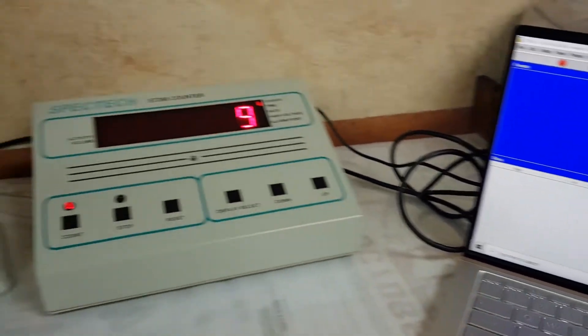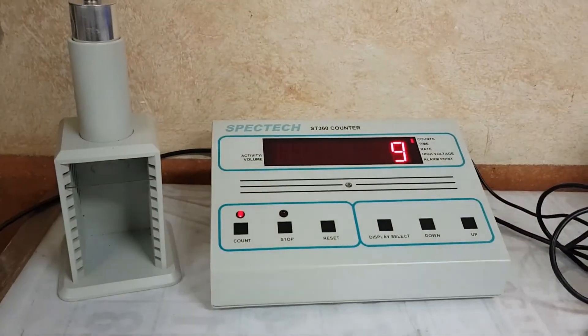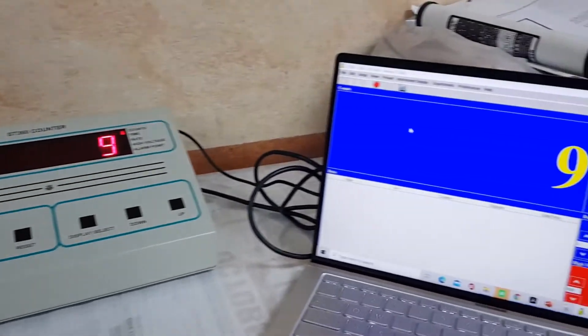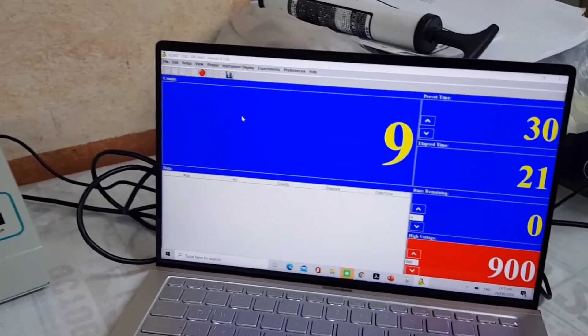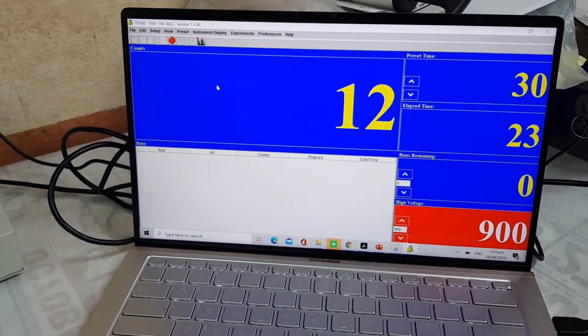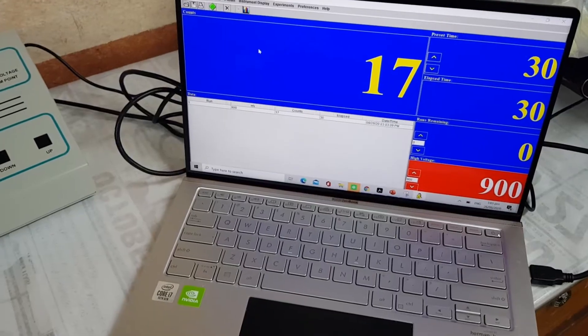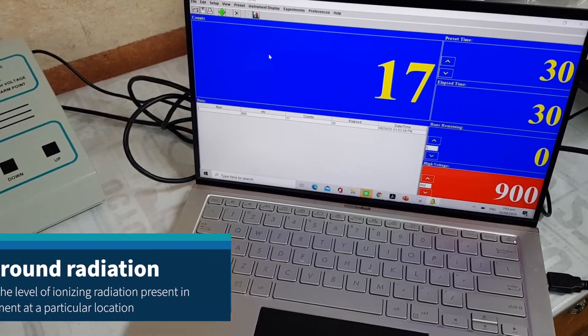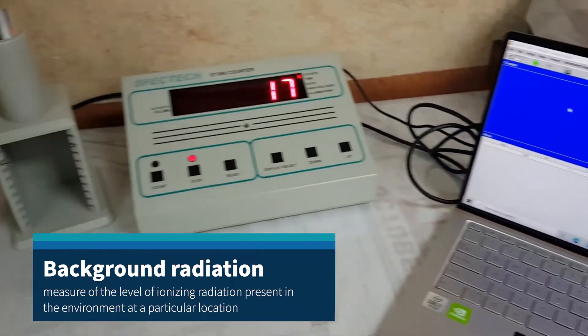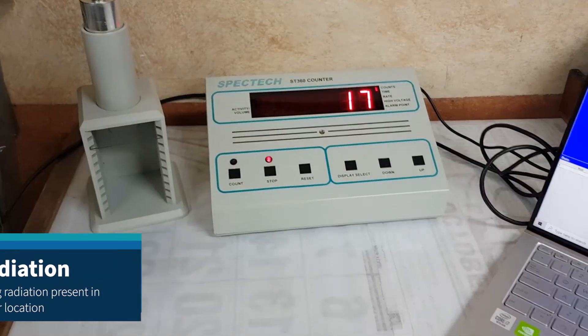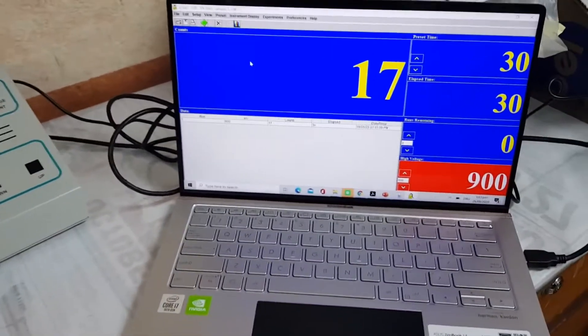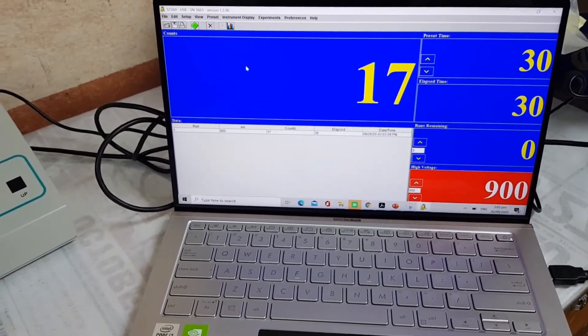From the preset menu, we set the runs to zero and preset time to 30 seconds. Then we run without a radioactive source to determine our background level. After running the setup for 30 seconds, we were able to get 17 counts as our background level.